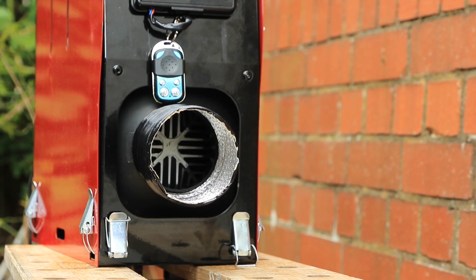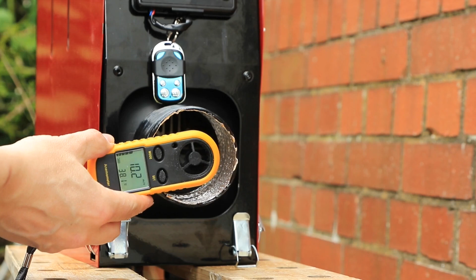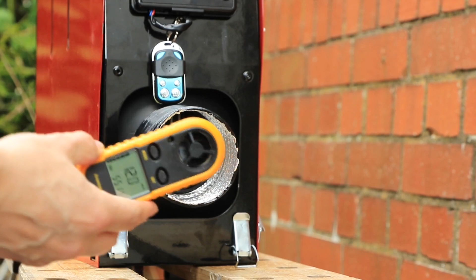So what I'm going to try and do now is just get some airflow readings from the heater, just to see how much air is pushing through. So the airspeed here, that's measured at 10.4. Obviously there's a lot of airflow coming around the heater. If I were to block this completely, I can't do that because it kind of burns my hand. But that went up 18-19 meters per second, so there's a lot of air coming through here. If I do this on the inlet, I get typically about 2.5 meters per second. If I come down to the outlet here, just pan the camera down.